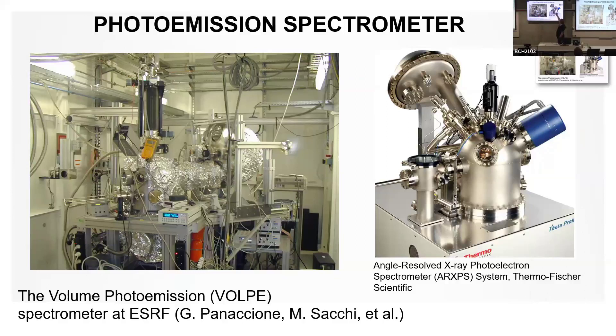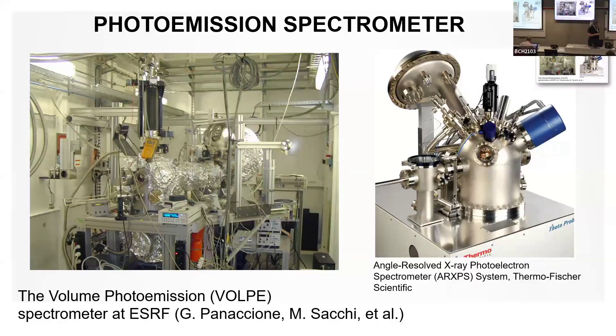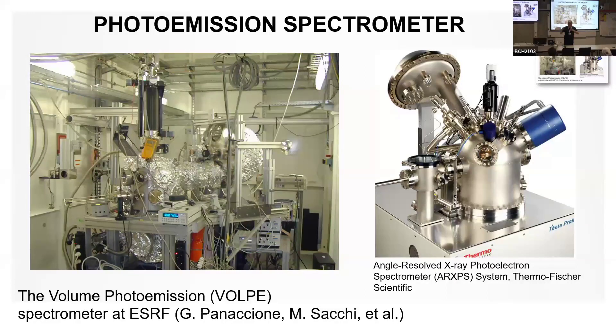The instruments must operate in ultra-high vacuum — this is very important because the inelastic mean free path of electrons is very low even at atmospheric pressure. The system is often wrapped in aluminum foil for baking: heating coils beneath the foil allow heating the system before an experiment so that dirt from interior surfaces outgasses into the pump. If the electricity of a beamline goes down, all the pumps stop, and losing vacuum everywhere is a big disaster requiring several weeks to clean up.